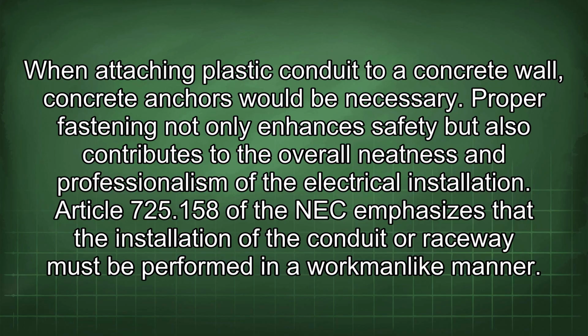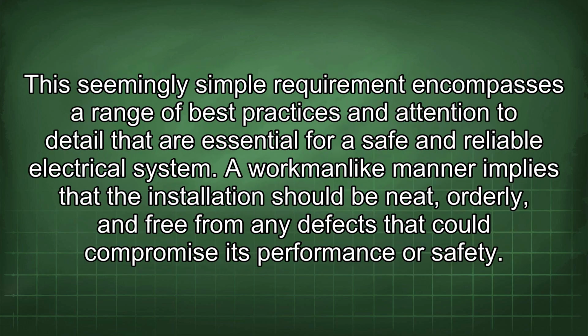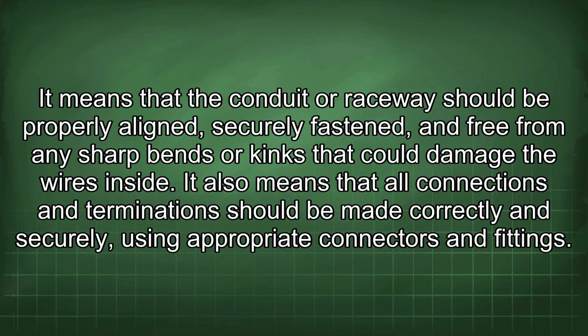725.158 of the NEC emphasizes that the installation of the conduit or raceway must be performed in a workmanlike manner. This seemingly simple requirement encompasses a range of best practices and attention to detail that are essential for a safe and reliable electrical system. A workmanlike manner implies that the installation should be neat, orderly, and free from any defects that could compromise its performance or safety. It means that the conduit or raceway should be properly aligned, securely fastened, and free from any sharp bends or kinks that could damage the wires inside. It also means that all connections and terminations should be made correctly and securely, using appropriate connectors and fittings.